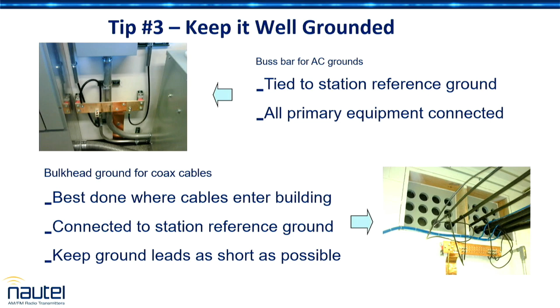Okay, grounding - short straight runs, don't do them like this. You don't need ground loops, and do not run your ground wire through a steel conduit if you can avoid it. Now if you're in a high rise and they have to have the ground wire enclosed, use PVC, because we don't want to create a ferrite. We don't want to add resistance to the path we want our lightning to take.